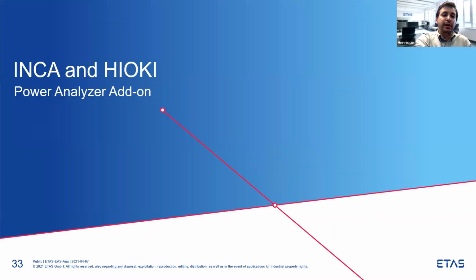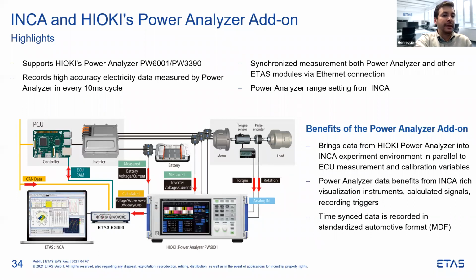And for the integration with the HIOKI Power Analyzer, we have recently developed an INCA add-on that supports the Power Analyzer PW6001 and PW3390 that Kevin mentioned before. The add-on brings data from the Power Analyzer into the INCA experiment in cycles of 10 milliseconds. This way, calibration can be performed having measurements from the Power Analyzer in parallel with ECU data and also from the other sensors. Efficiency loss and all the additional data from the Power Analyzer can be used as an input to INCA, and INCA can calculate signals with that or manage recording triggers. And all this data is synchronized and recorded in a standardized automotive file format, the ASAM MDF.